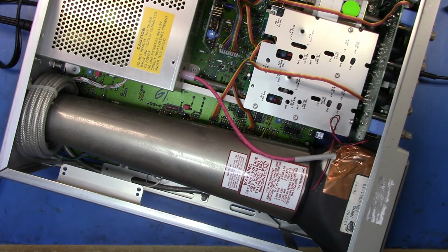Typically when you send away to the manufacturer for a calibration, the manufacturer calibration will include the calibration and any adjustments required to bring the device back into calibration. And so they'll basically try and calibrate the unit and adjust it, and then if they can't calibrate it, at that point they'll generate a fail for the calibration and they'll ask you whether or not you want to repair it. I sent away an 8902A to Keysight, and that was basically the same thing that they did. They went through it and they said everything calibrated except for the input amp, SWR and amplification. Would you like us to give you a quote to repair that input amp? And I had them do that, and the quote was $8,000, which I didn't take them up on, but the point is that they will try and do the adjustments to the unit.